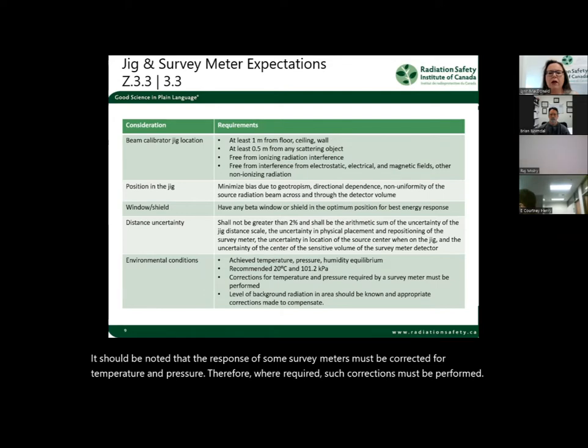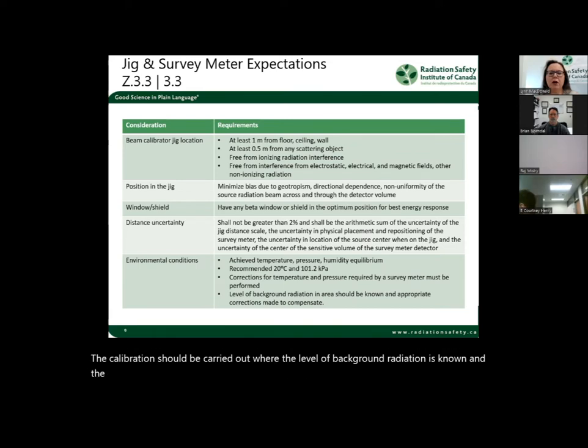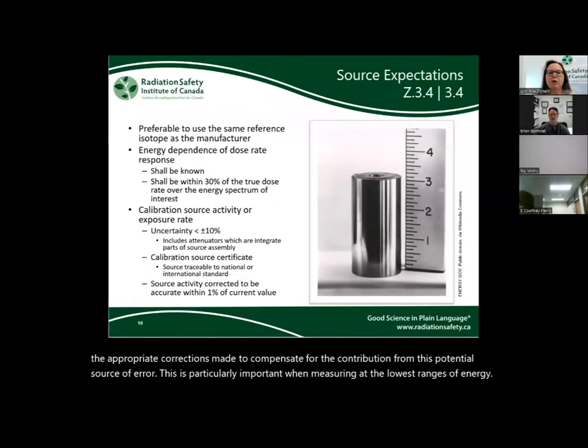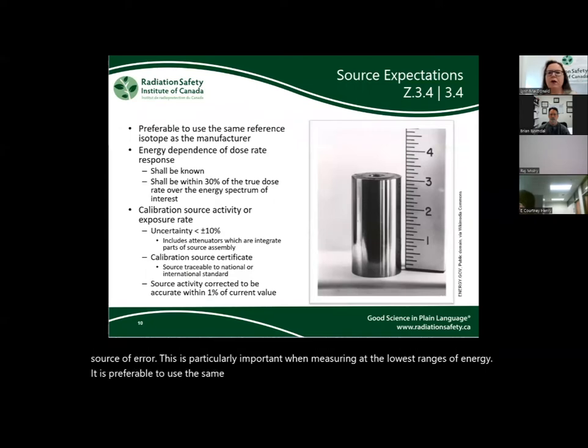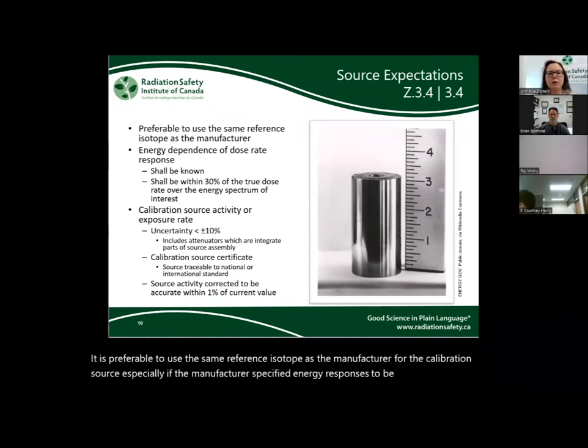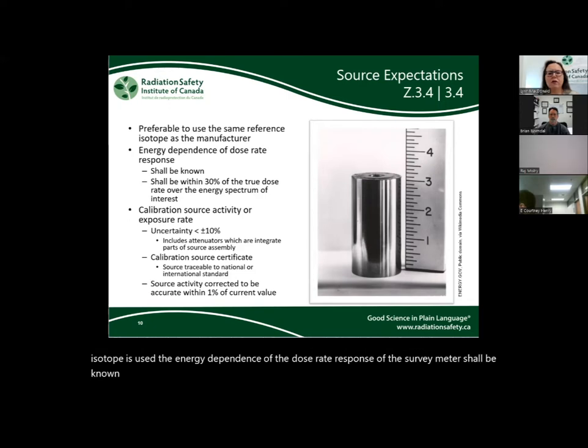The calibration should be carried out where the level of background radiation is known and the appropriate corrections made to compensate for the contribution from this potential source of error. This is particularly important when measuring at the lowest ranges of energy. It is preferable to use the same reference isotope as the manufacturer for the calibration source, especially if the manufacturer specified energy responses to be assumed. Whatever isotope is used, the energy dependence of the dose rate response of the survey meter shall be known and shall be within 30% of the true dose rate over the energy spectrum of interest.